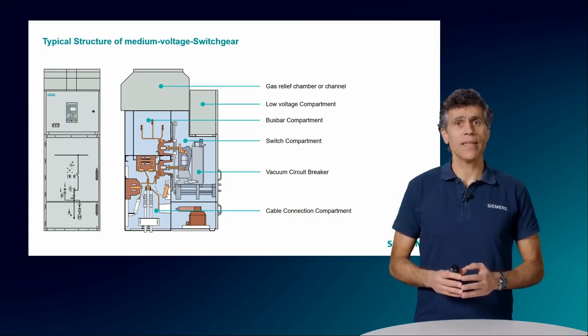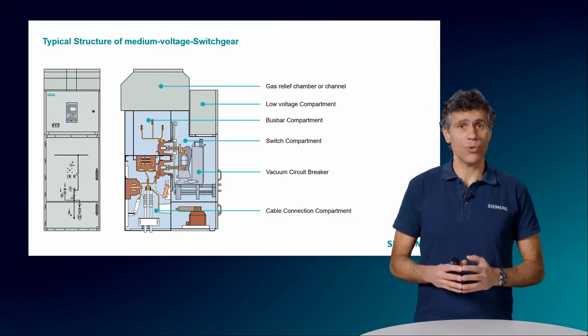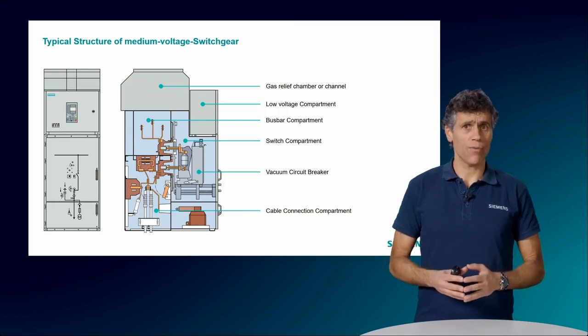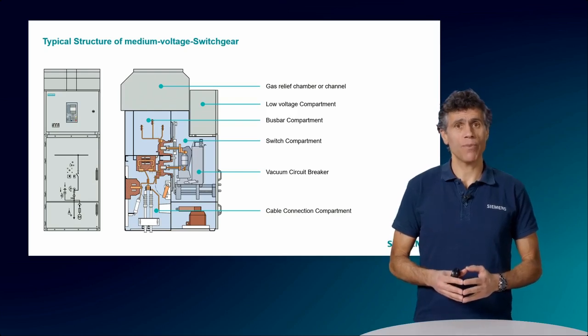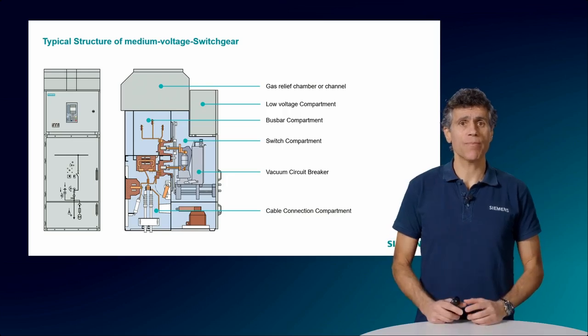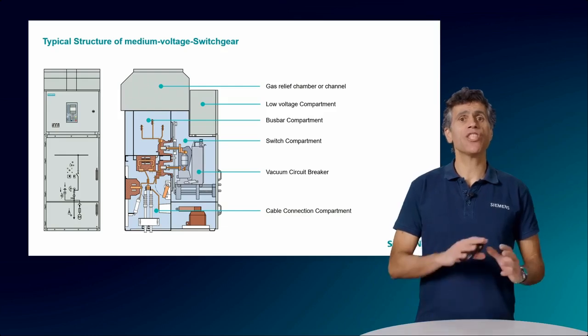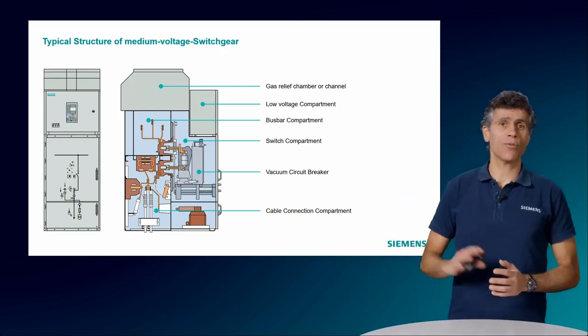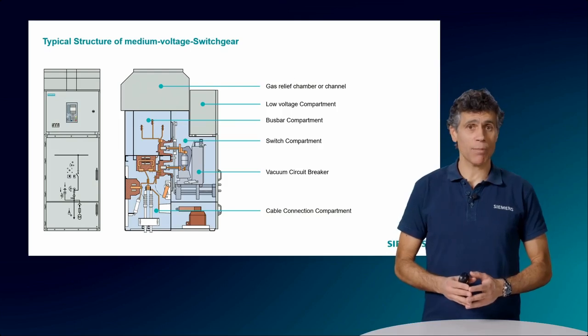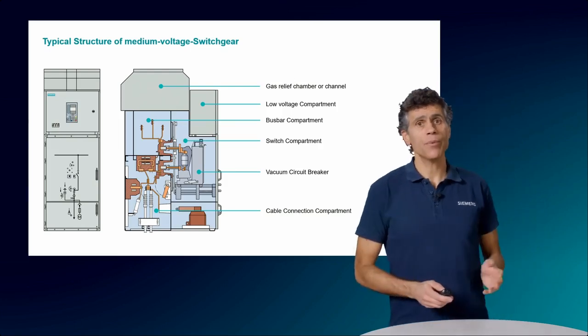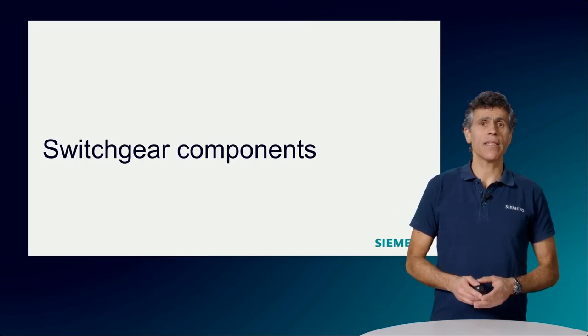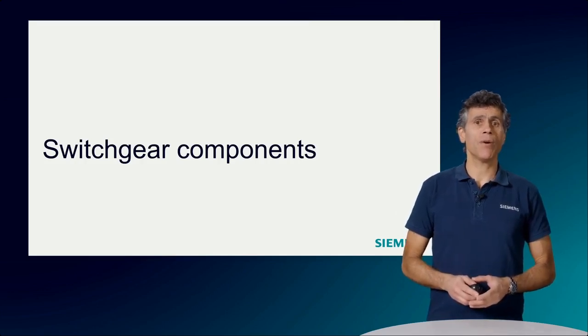And finally, there may be a gas relief chamber where the gases are led into in the event of an arc fault, which causes a big explosion if it's not switched off before. This compartment may be common to the whole switchgear or individual per panel. When it's mounted over all panels, it builds a channel that leads hot smokes and gases to the outside of the switchgear room in case of an explosion. So here we go. Let's have a look inside a typical switchgear and find out about its components.